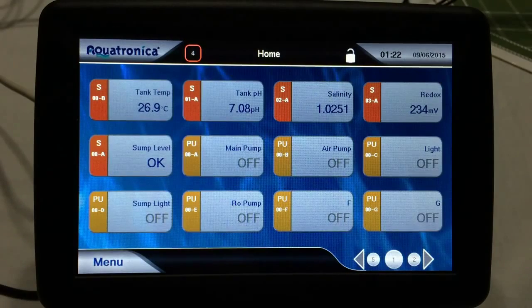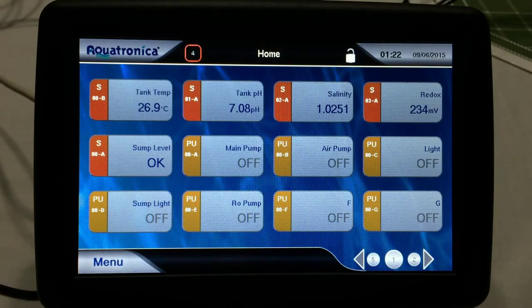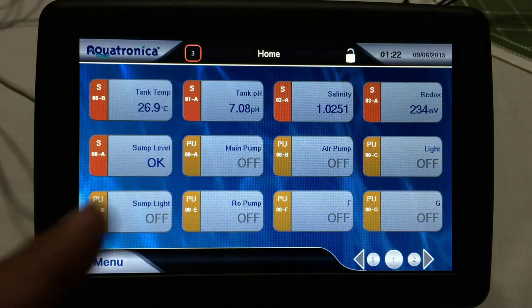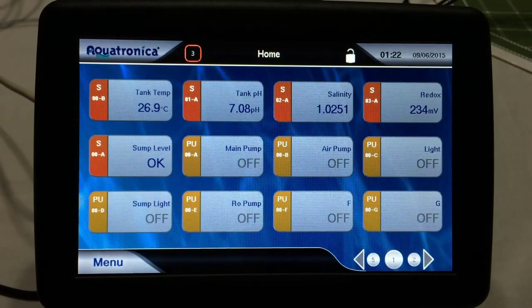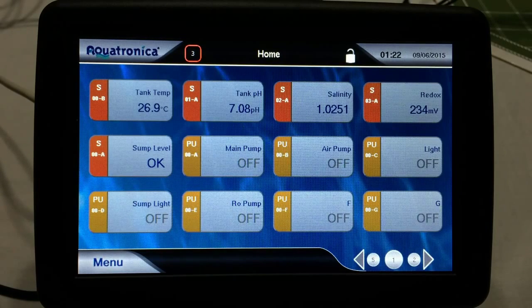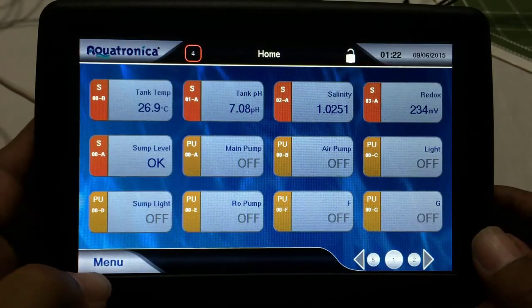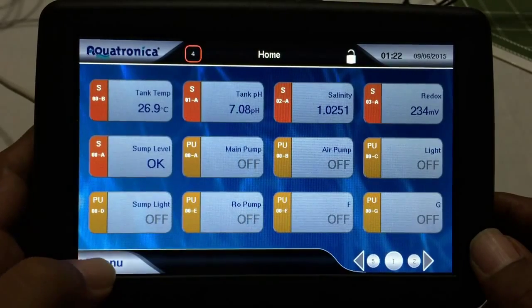Okay, the probe has been sitting in there for about 5 minutes in the 7.01 pH fluid, and it's reading 7.08, as you can see. So possibly the calibration is not all that far off straight out of the box, but typically it's not going to be that accurate. You're going to definitely need to calibrate probes, pH probes.